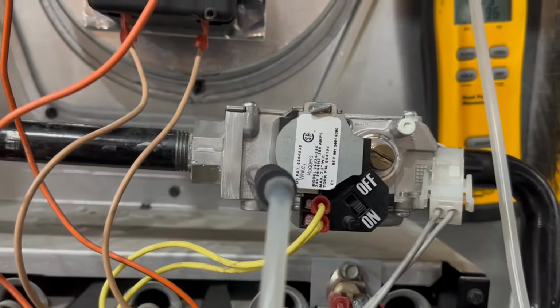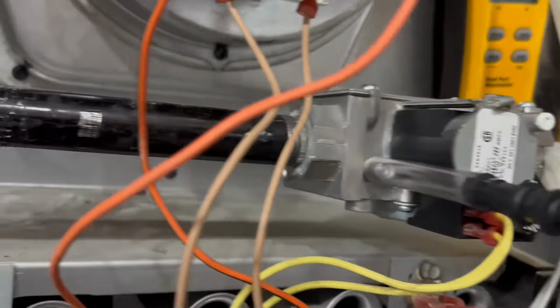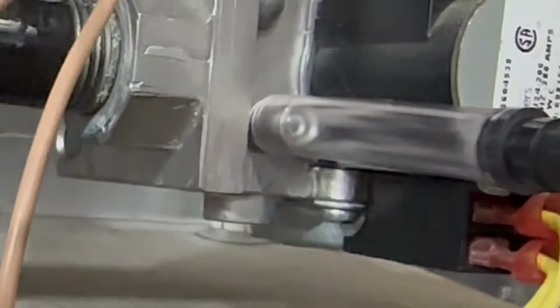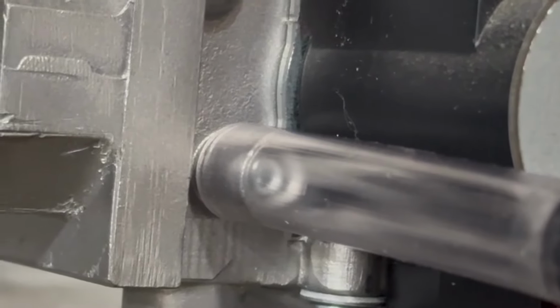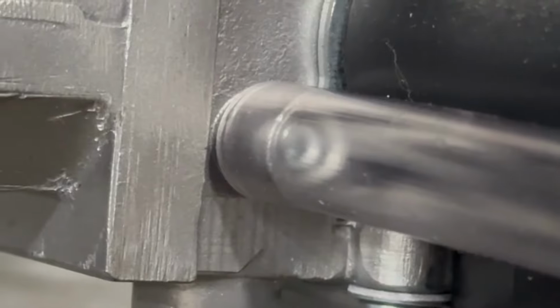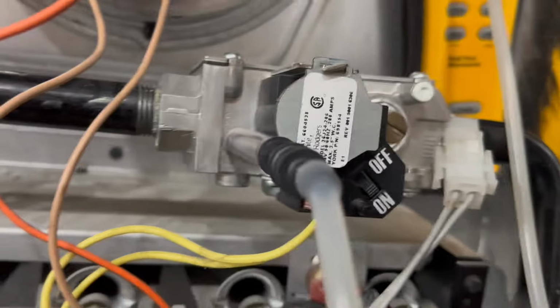We want to make sure we're getting incoming gas pressure. So you see, I literally put it over the whole part there. And because I cracked it open, that gas is seeping through around that little Allen nut. It's seeping through enough to create that gas pressure. You don't need to take that Allen nut out completely. You just crack it open.